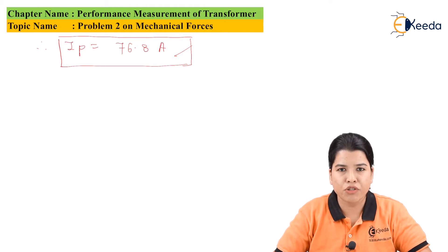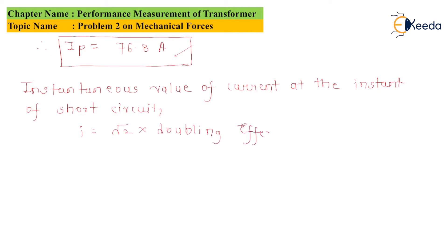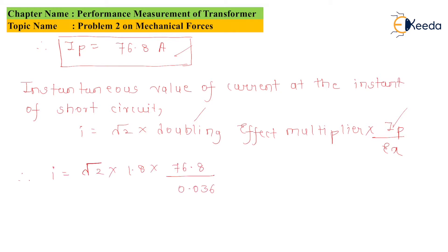Now let us find the value of the instantaneous current at the instant of short circuit. The formula is: I = √2 × doubling effect multiplier × Ip / Ea. Substituting the values: I = √2 × 1.8 × 76.8 / 0.036. After solving, we get the value of I.